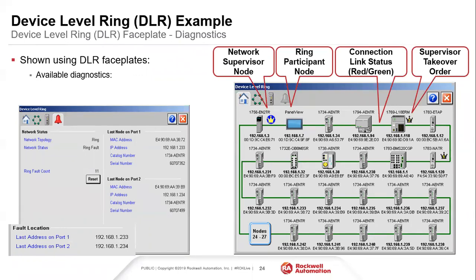So for anybody that doesn't know, an AOI is just an add-on instruction, a little black box of code that we provide to you. It's on our website. You can download it. What this does is it not only tells you your network supervisor, it will assign and tell you what any of your backup supervisors are, because we do have those. It will provide you a status uplink. It will tell you where the backup supervisor is located, and it will tell you the IP address and MAC address of every single one of the devices that are there.